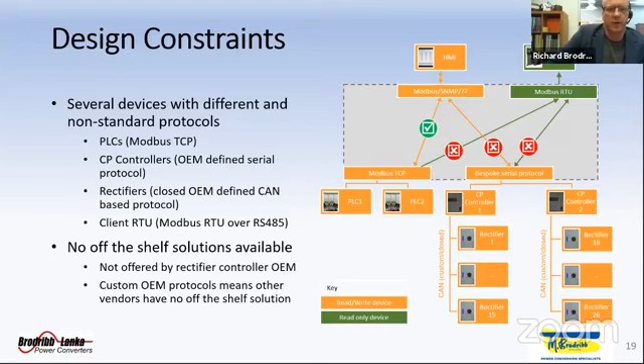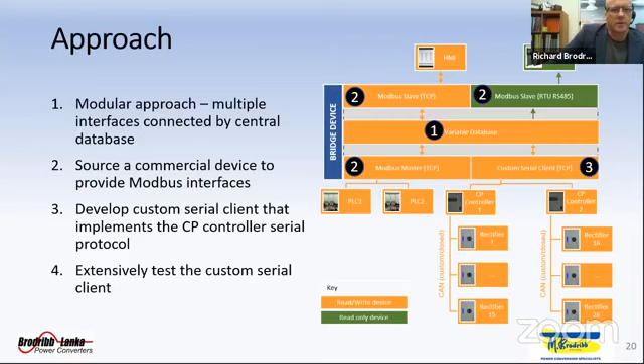We sourced a commercial device which was able to communicate on Modbus and a range of other industrial protocols. And then we needed to develop a custom serial client that implemented the CP controller OEM serial protocol so that we could talk to it. Obviously, the key risk in this system would be making sure that we had a robust solution for that custom serial client. So extensive testing was a key feature of what we looked at for this.